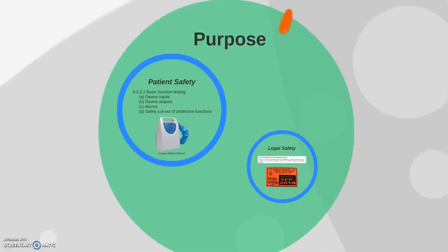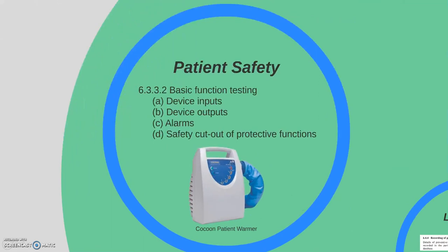There are two main purposes of the AS3551 standard: patient safety and legal safety. There are many standards in the AS3551 that relate directly to the safety of the patient using the machine. One of the standards is 6.3.3.2, Basic Function Testing. This standard includes all of the elements of a medical device that must be tested to ensure patient safety.